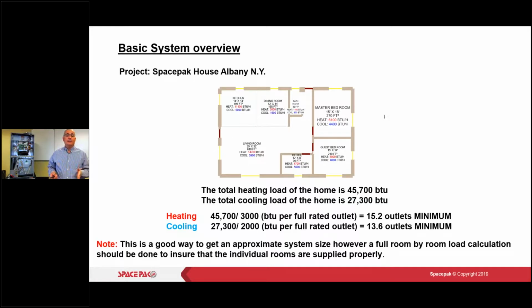And SpacePak does have pre-sale support. If you have a set of plans you want to send to them, they can help you design out the system. So here's a basic overview of the design. The job was designed for 45,700 BTU for heat, 27,300 BTU for cooling. At 3,000 BTU per outlet rated full capacity for heat, I would need 15.2 outlets minimum. Cooling, I need 13.6 outlets minimum.